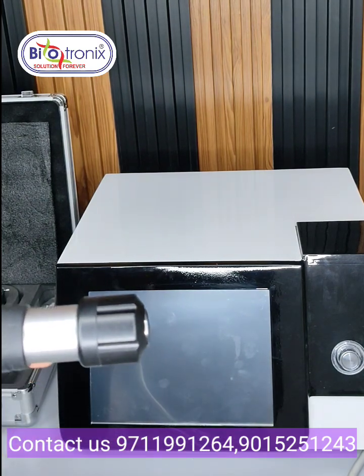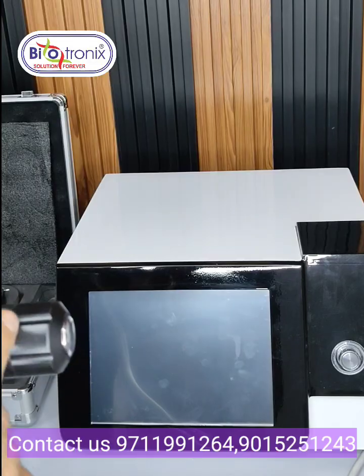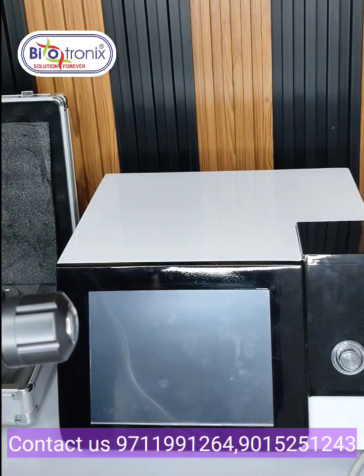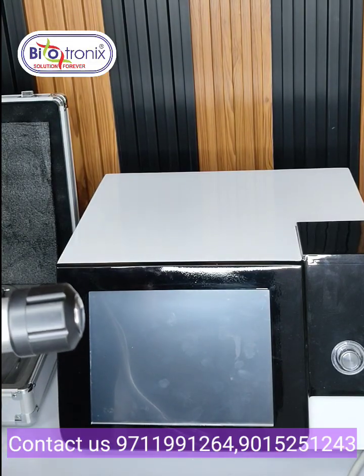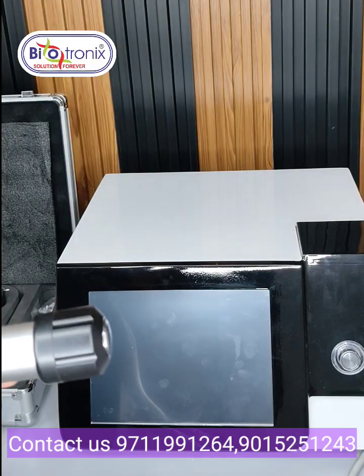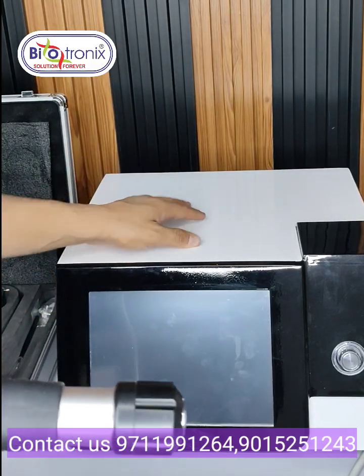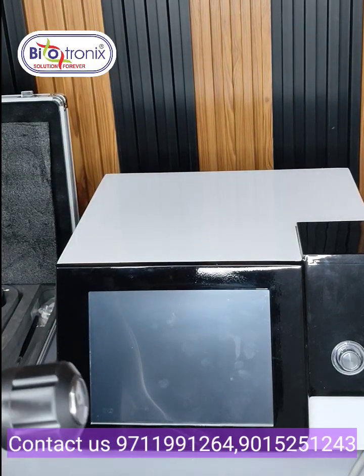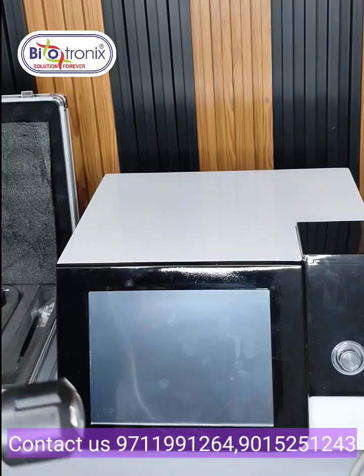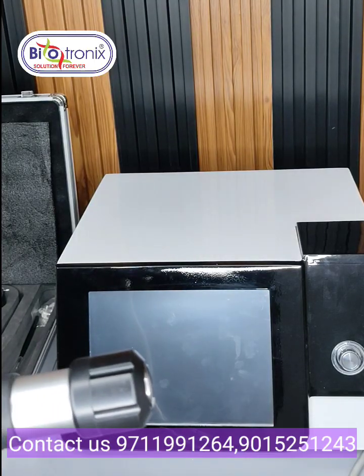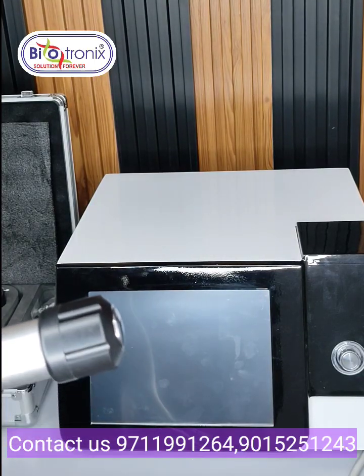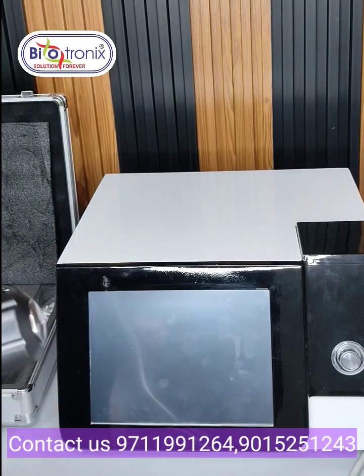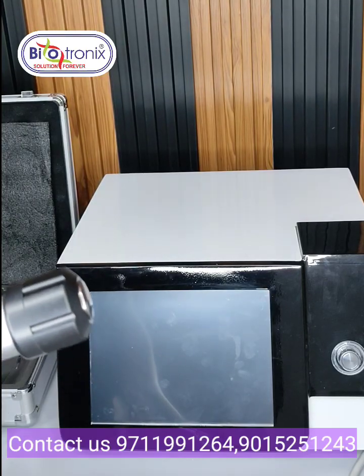You can see the bullet travel from here to there, and when it strikes the surface, because of the compression and pressure created in the device, it strikes the surface and generates the shock wave. And while other bullets in the shock waves give you around 2 lakh to 2.5 lakh shots, this bullet provides you around 3 lakh to 4 lakh shots per bullet.